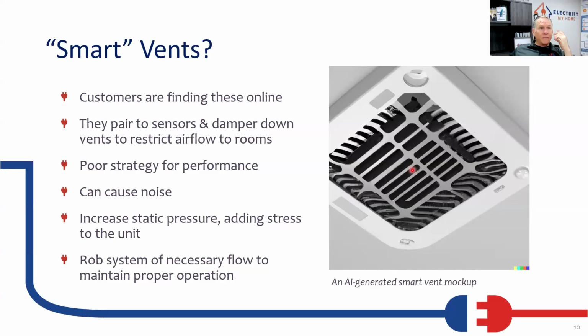So there's at least going to be less noise, and it can redirect the air down through the other ductwork better, rather than sending it down there and having it stop at the end and build up a bunch of pressure in the duct, and then having to overcome that pressure and go into the others. If we shut the damper right off at the plenum, all the air is going to go right down through there, so we save tons of energy not pressurizing that extra duct. It's not an insane solution, but it's going to have a backward compatibility problem. I don't know if any of you have seen these new registers that you can put on the wall and put the mud around them so they look like they're part of the wall. Those things are terrible too, because they cut the airflow too much. They look beautiful.